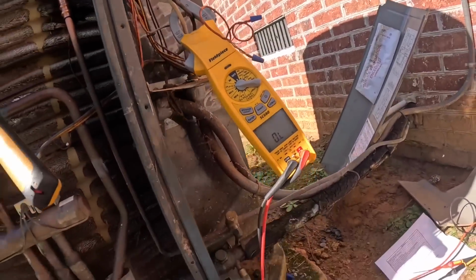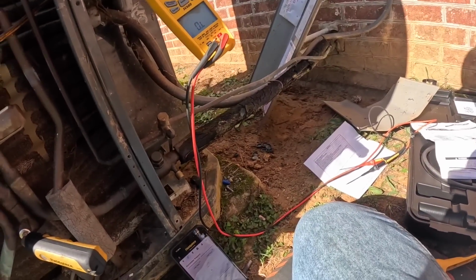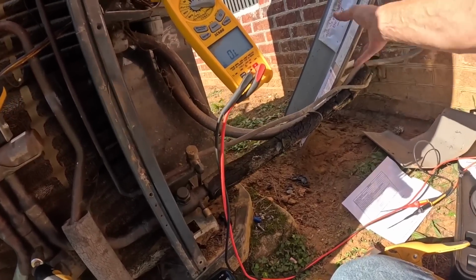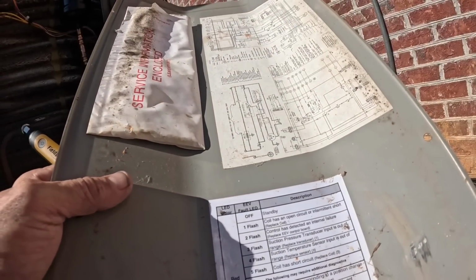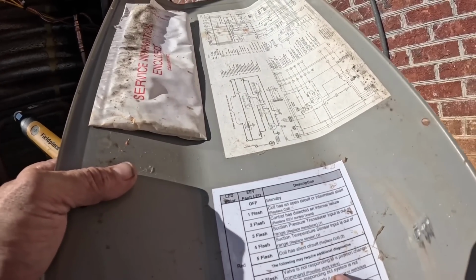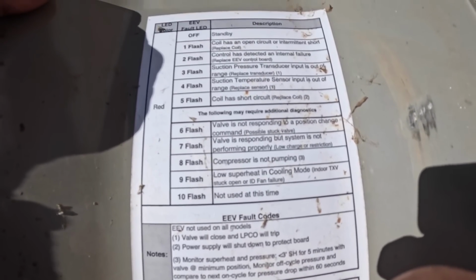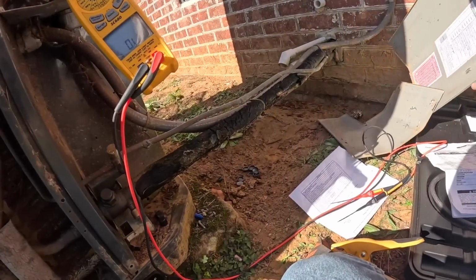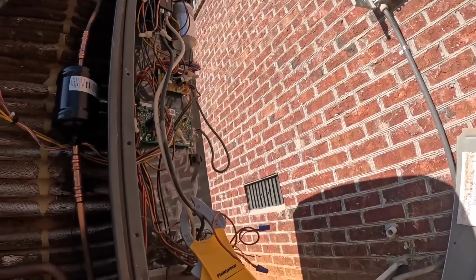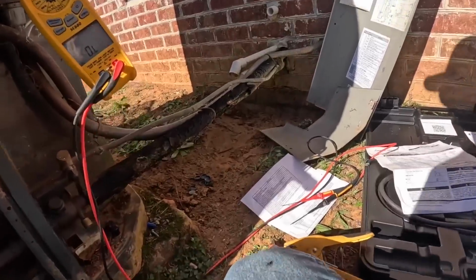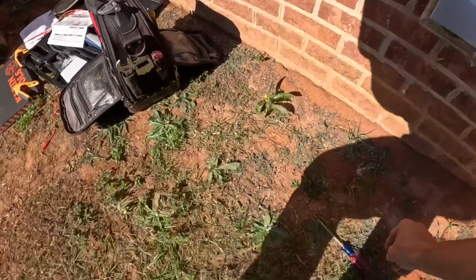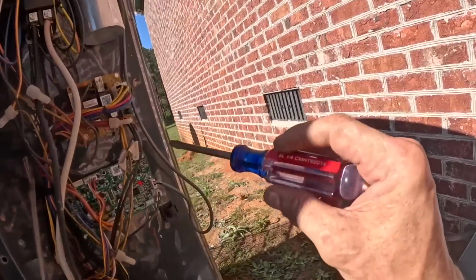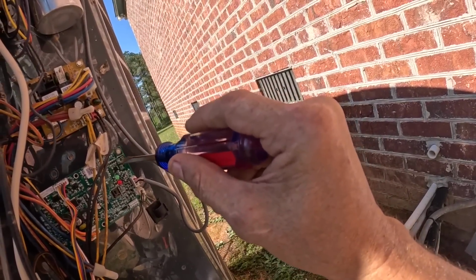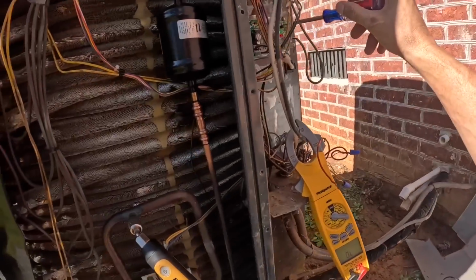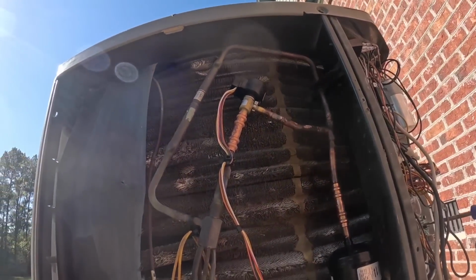Six and nine. Six, valve is not responding to a position change command. Possible stuck valve. Low superheat in cooling mode. Let me get my screwdriver and see if we can't force it to open. It's opening up.